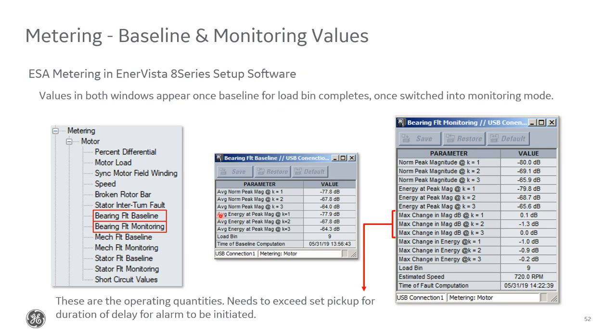Once the baseline recording is complete and we switch into monitoring mode, then we go over to this monitoring window here. This screen will update and it'll show you the values based on the latest sampling. So what you're interested in here are the normalized peak values shown at the top. We take these values, we compare them to the values you see in the baseline window, and this change value is stored in the highlighted max change register. So that's this area here.